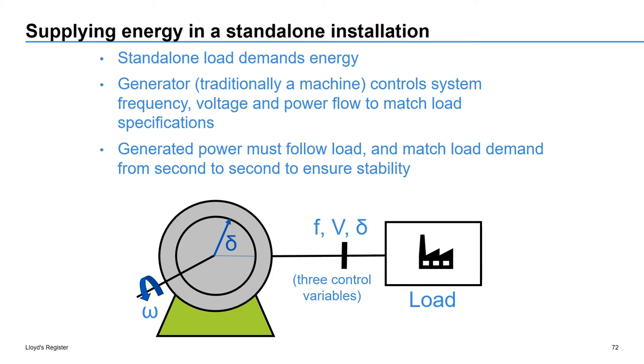So in a standalone system, one has essentially one generator or small number of generators. Traditionally, they'd be machines supplying a single load. And those generators have complete control over the fundamental parameters of the system. The frequency and the voltage are directly controlled by those single or small number of machines. And the fundamental control problem is then just to ensure that the generated energy matches the energy demanded by the load from second to second.